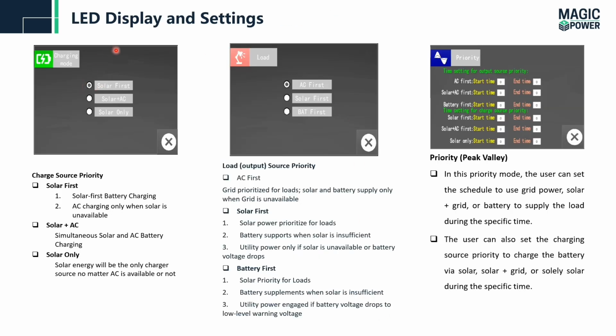Here we can see the charging modes of the battery. Basically, in the charging mode we choose how to use the system, for example the PV generation and the power grid. Which one do we want to prioritize for battery charging? It could be the power grid or solar panel generation. Solar first means solar will be responsible to charge the batteries, and if solar is not available, the power grid will be responsible. In the case of solar and AC, both charge the battery simultaneously. And solar only means only solar generation will charge the batteries.